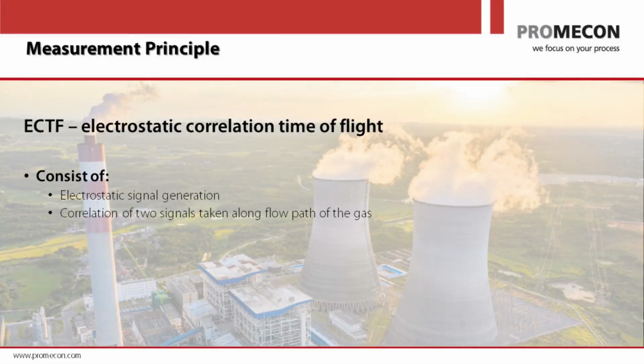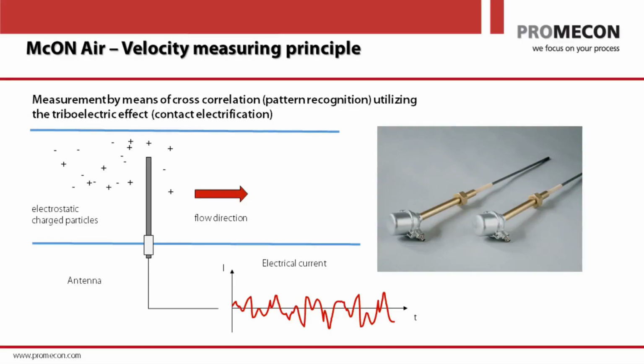Basically, we have a correlation-based measurement, and the correlation is done by a digitized signal that we get from our sensor. So we have a signal, we digitize it, and the digitized signal goes through a digital correlation algorithm. So it's all a digital measurement that is not prone to any drift or any deviations over time. And I will explain exactly how that works. The other thing is the signal generation is done by an electrostatic signal that we get from the gas. And let me explain how that works.